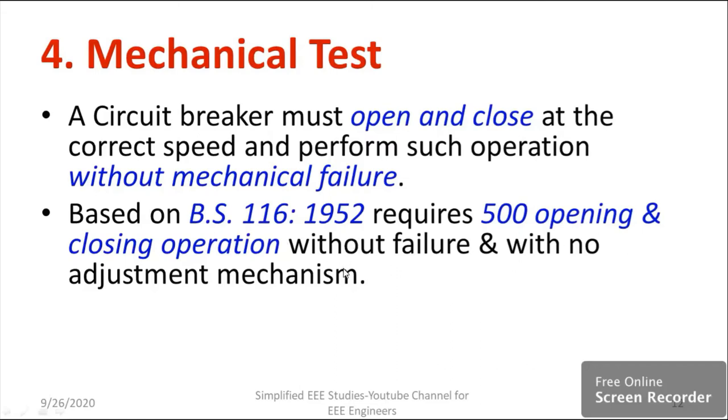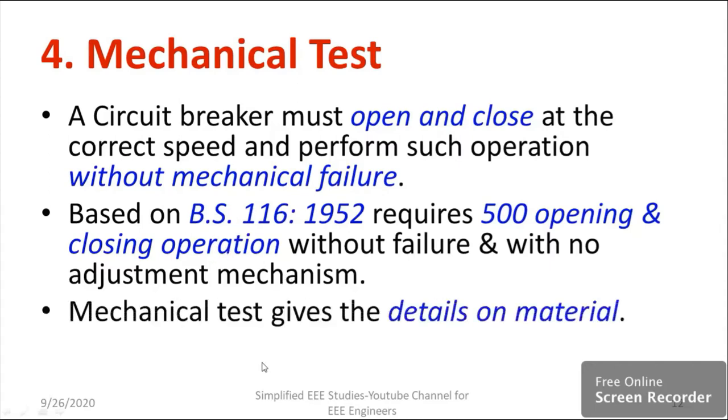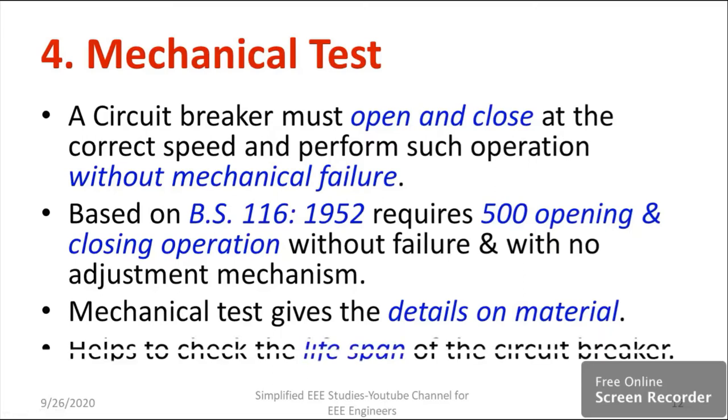If any observation is not comfortable, if you have observed anything, that means your test piece is not fine. So for fine operation, at least 500 openings and closings should take place without damaging the fixed or moving contact. So that's the scenario for this standard. The mechanical test also gives details on material: what type of material you are going to use to make that particular fixed contact and moving contact. So these are the importance of the mechanical test. It helps the lifespan of the circuit breaker.